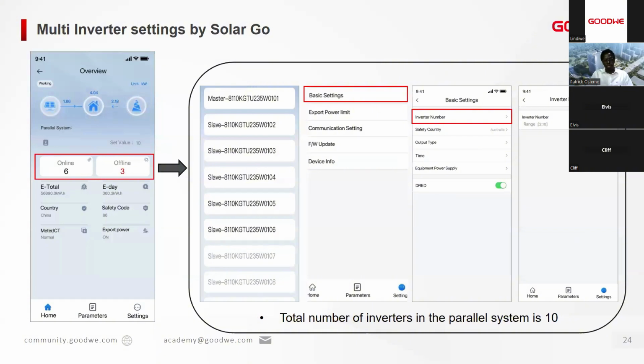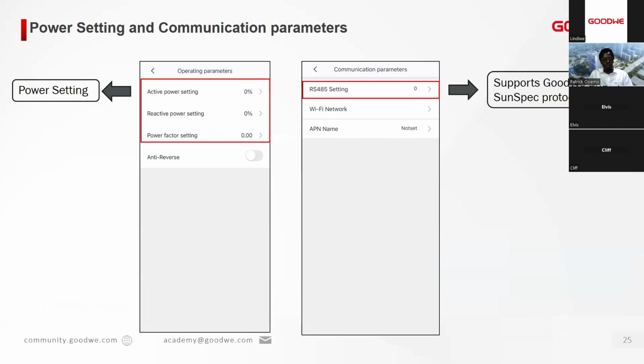Then in case you have multiple inverters, you can also check them through the same system, or you can use it during configuration either with SEC or the EZ-Logger Pro. It is similar to the single inverter. You can also do the same with multi-inverter settings on the SolarGo. The types of settings that you can do are on active power. Mostly we recommend you set active power to 100% so that you can maximize your production. And also, for most of our countries, you can put on the anti-reverse setting so that you are not exporting to the grid.